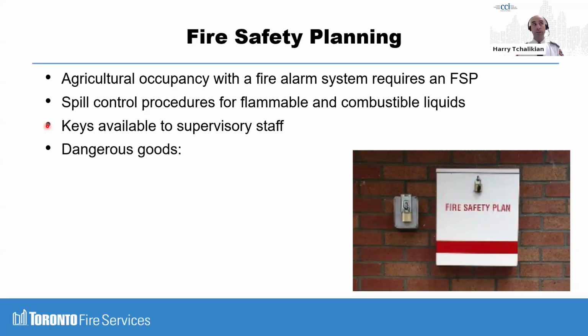Make sure you never put private rented spaces like tenant spaces, especially residential dwelling unit keys, in the fire safety plan box. We don't want them, and you can understand the problems that causes. They go missing, somebody steals it, now you have to rekey your whole building. We want service room keys to let me into the fire alarm room, sprinkler room, etc. And there's no issue. You know what the firefighters like to see. Firefighter rolls up on site, you're standing there with the keys dangling. Everybody's happy. Otherwise, they're in the fire safety plan box.